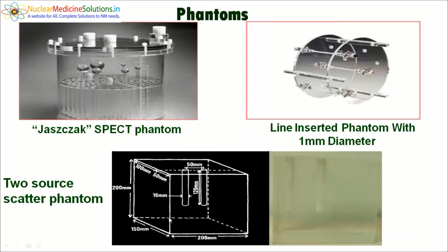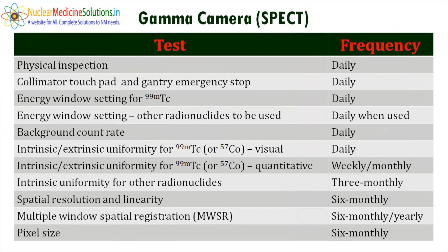This is a line inserted phantom which we use to check the spatial resolution of the SPECT or gamma camera. This is a scatter phantom which we use to check the dead time of the gamma camera in scatter medium. These are different reference books or reports which can be used while performing quality control or acceptance tests of the SPECT or gamma camera. So these are the different quality control tests listed in this table, which can be used to check the performance of the gamma camera or a SPECT.